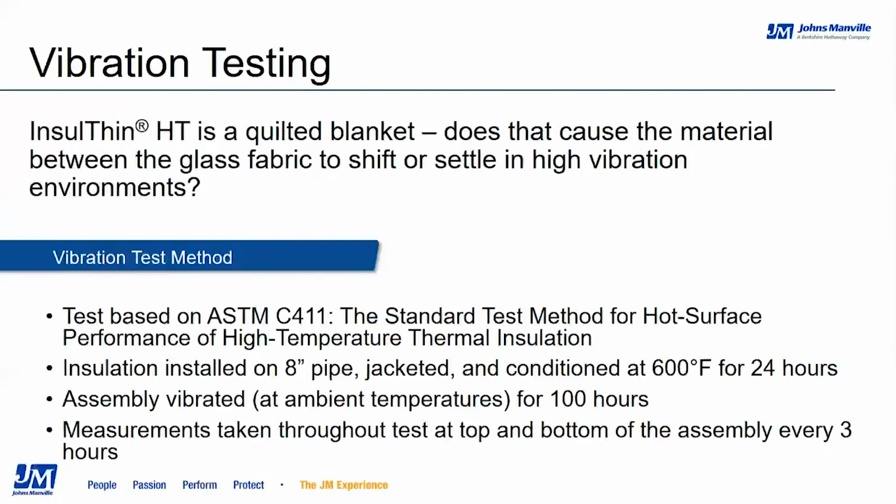So neither InsulThin HT nor silica aerogel have binder to burn out, but as Jeff has already explained, InsulThin HT is a quilted product with fumed silica particles between the needled E-glass fabric layers. And this has led to the question about whether or not the material between the needled E-glass fabric will shift and settle in a high vibration environment, having a negative impact on the insulation's thermal performance.